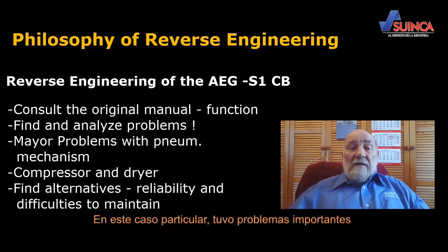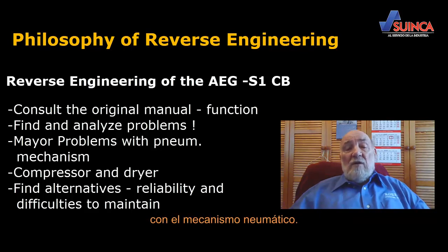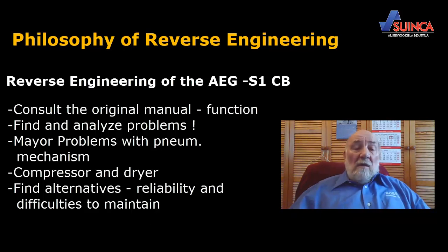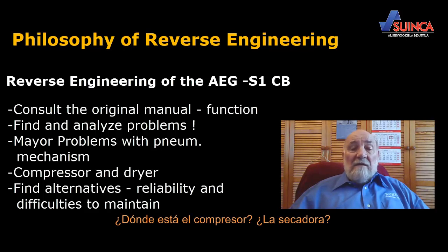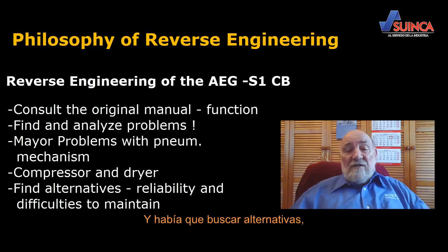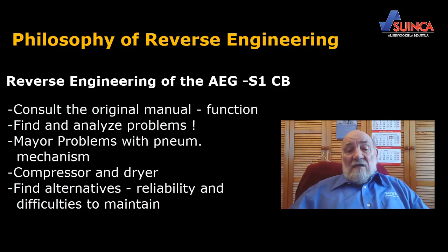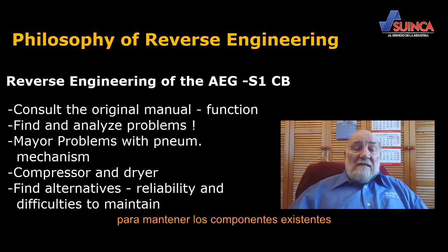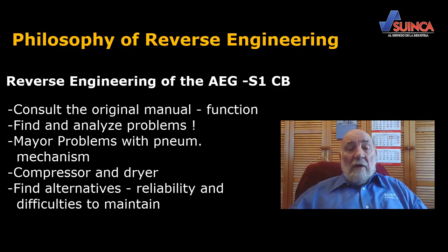In this particular case, we had major problems with the pneumatic mechanism, with the compressor, the dryer, and we had to find alternatives, because of reliability and difficulties to maintain the existing components.